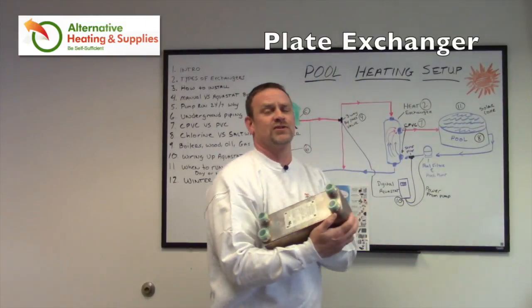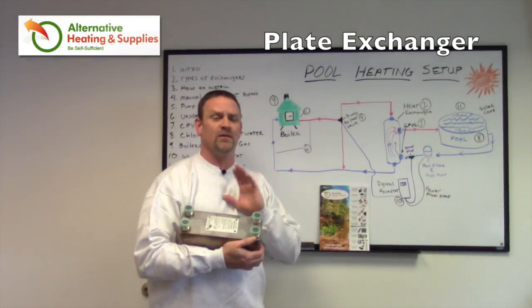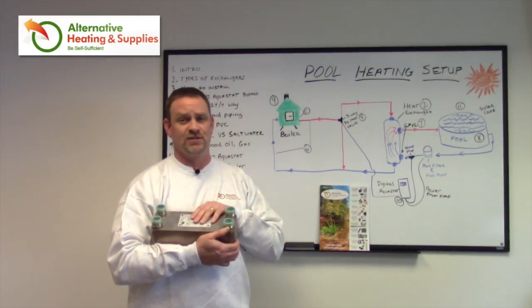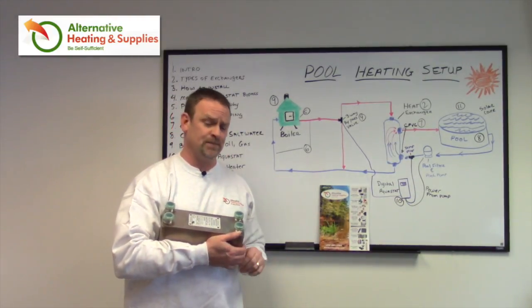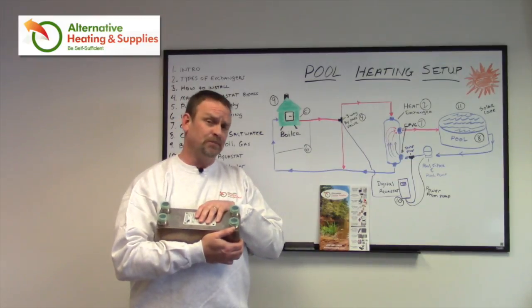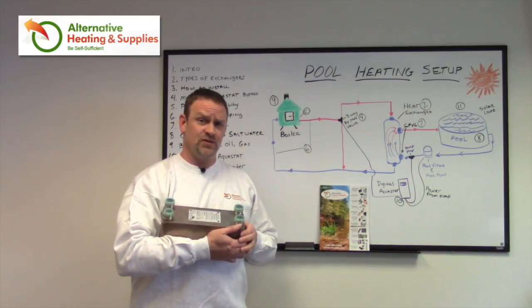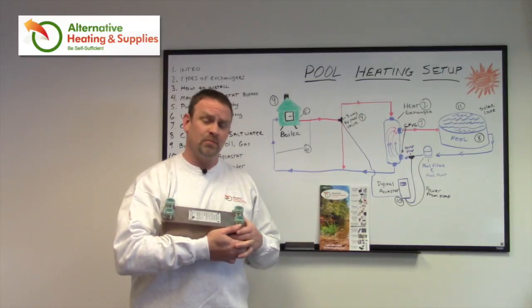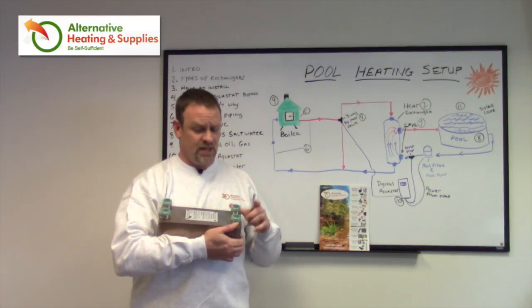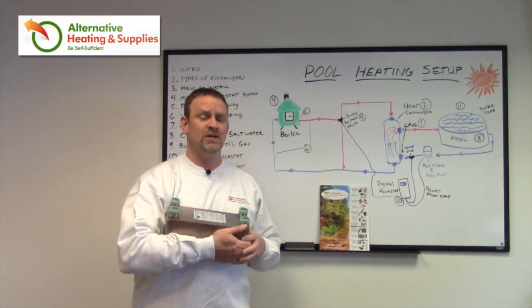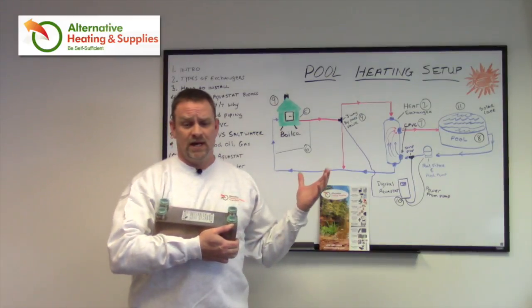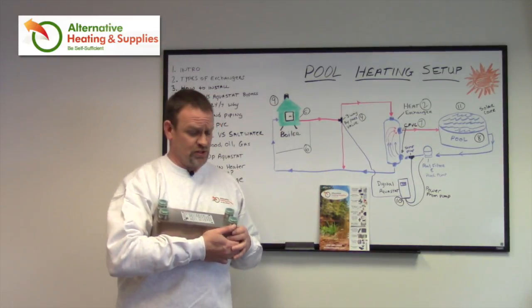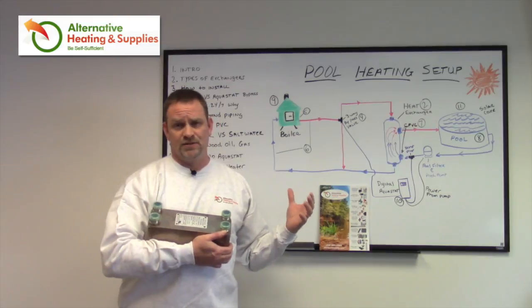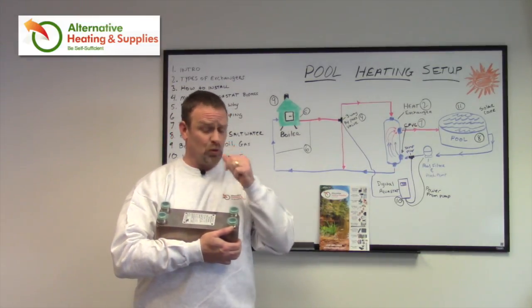The other heat exchanger is called a plate exchanger. This is one of the ones that most people ask me about because it is considerably cheaper than the tube and shell designs. They're also made from stainless steel. They have a lot more surface area, so they heat faster. The problem with them in a pool application is that the port sizes are only an inch. That means you can only get, depending on the pressure your pump produces, as much as 20 gallons a minute, which is not usually enough for a pool.